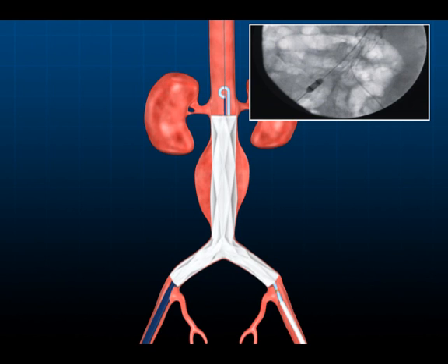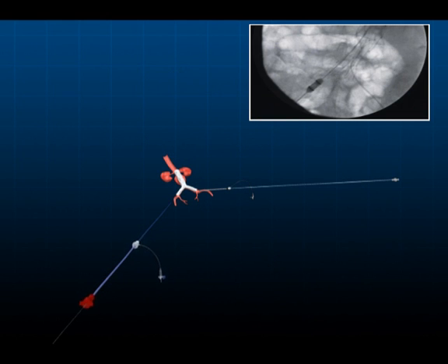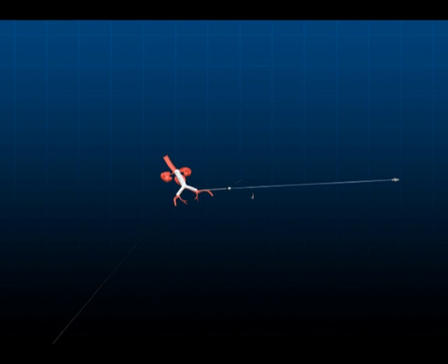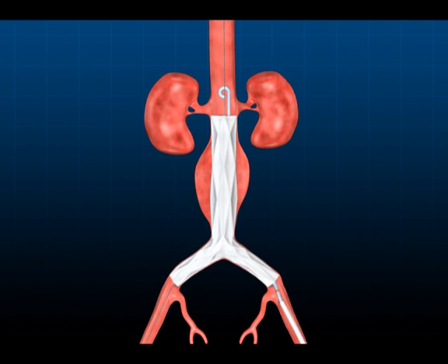Tighten both the white and red hub and remove the delivery system as a single unit by pulling back on the red hub. Insert a guide wire to straighten the pigtail catheter, then carefully remove under fluoro to ensure that the deployed stent graft does not move.